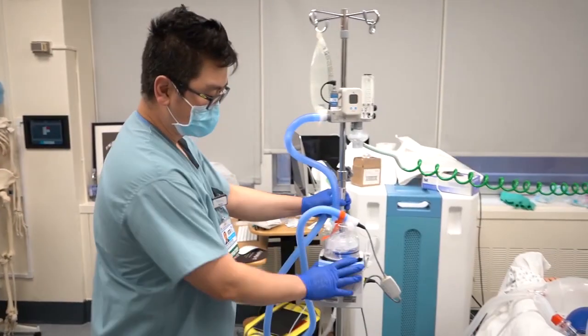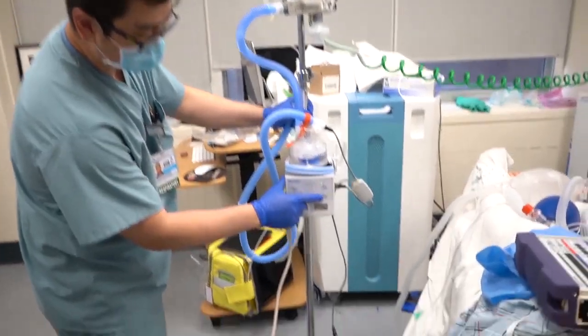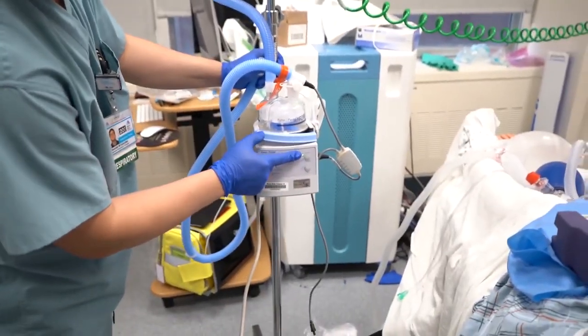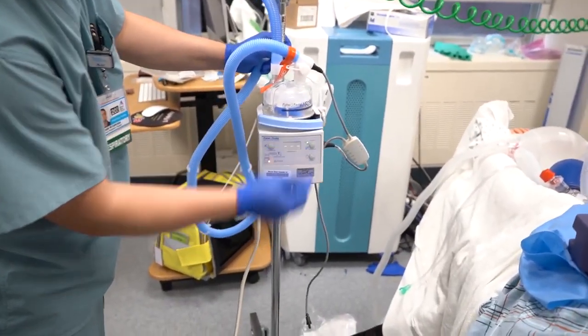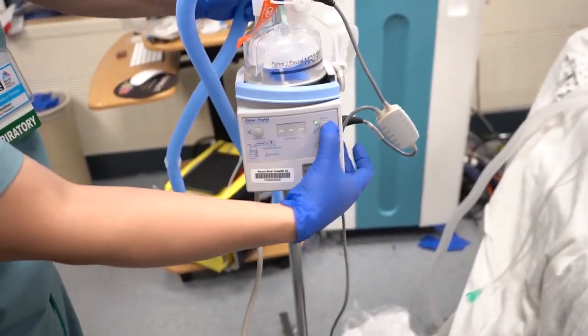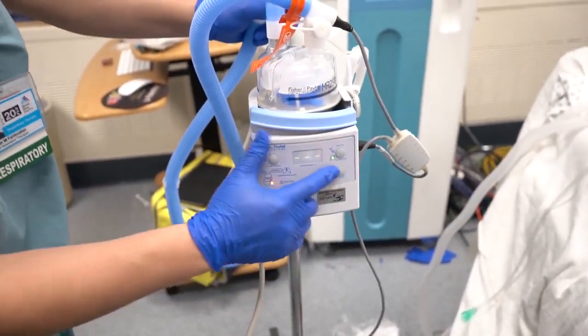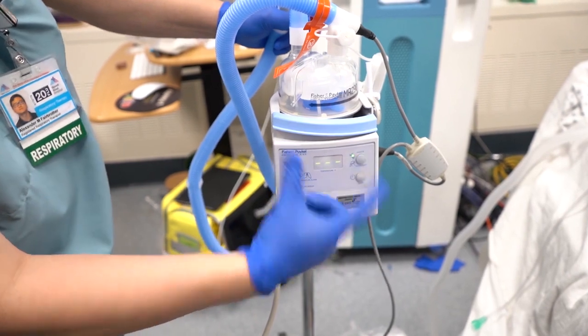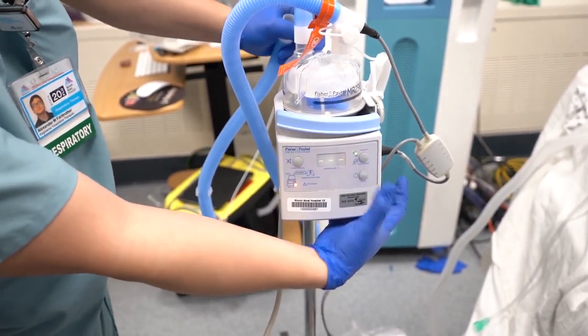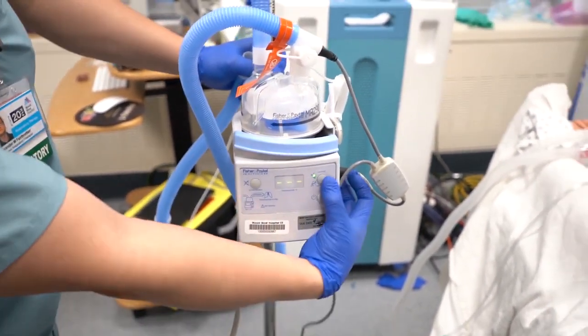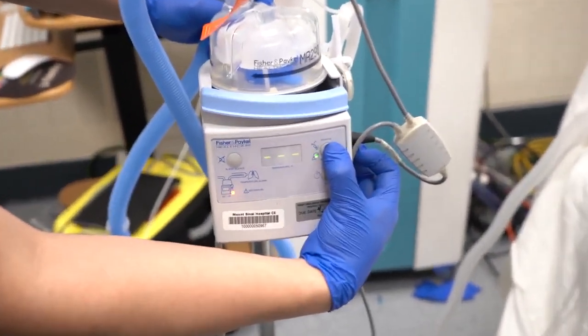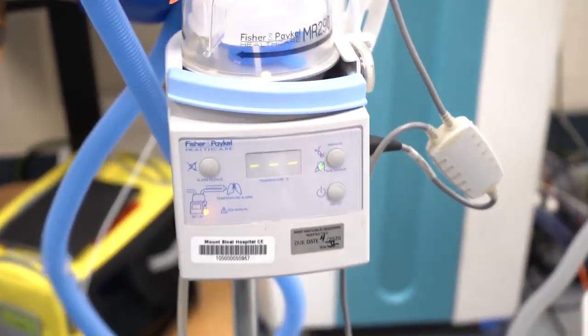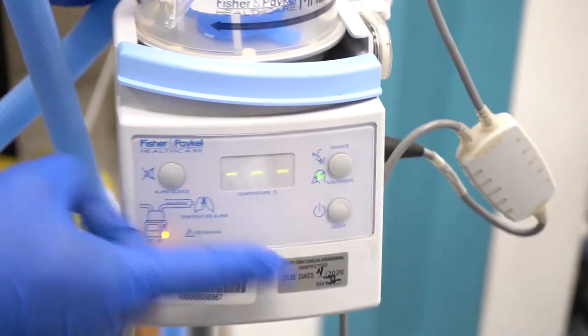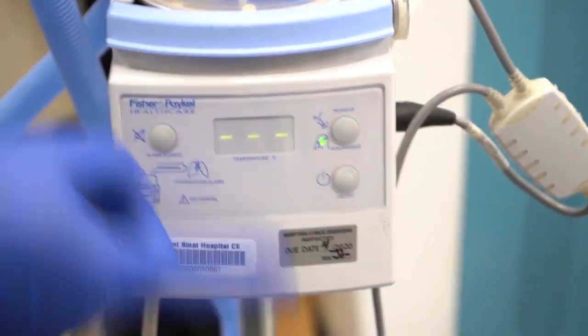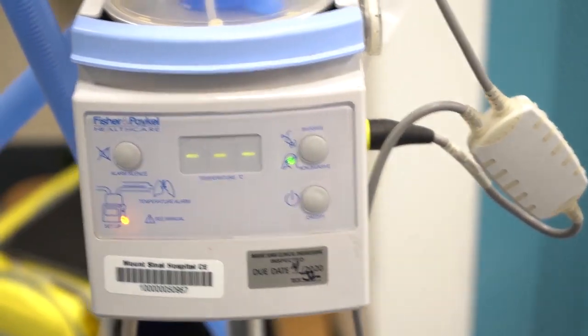Alright, so once the heater's on, there are 2 modes that you can select: invasive for an endotracheal tube, and non-invasive. If they're on a high flow, we're going to select non-invasive, so you're just going to press and hold until it switches. Right now they're on invasive, so we're going to switch to non-invasive. Just press and hold and it'll light up. The difference is that invasive goes up to 37 degrees, non-invasive only goes up to 31.